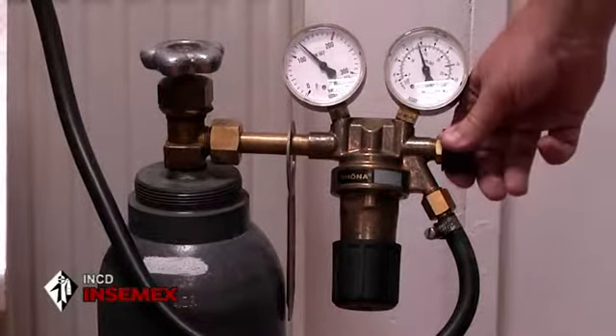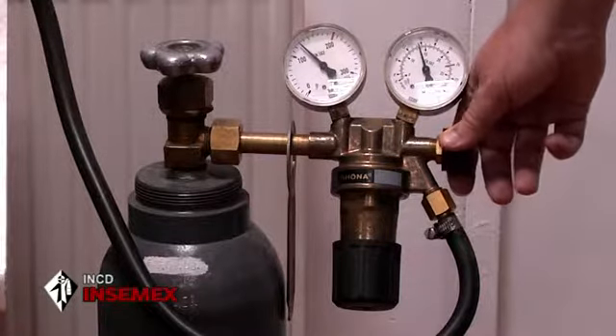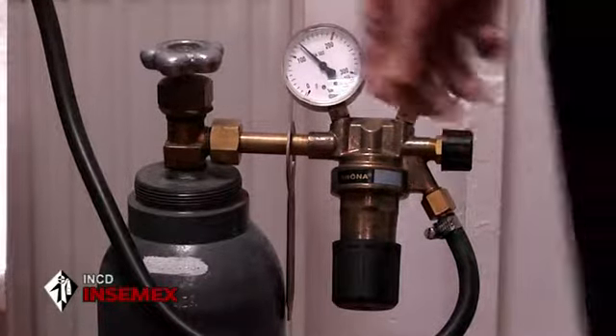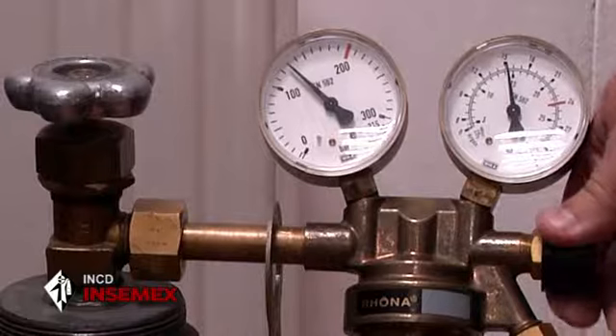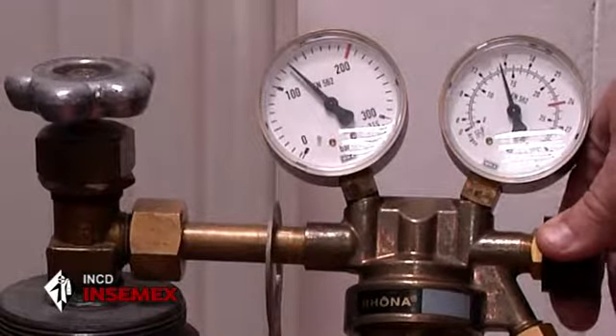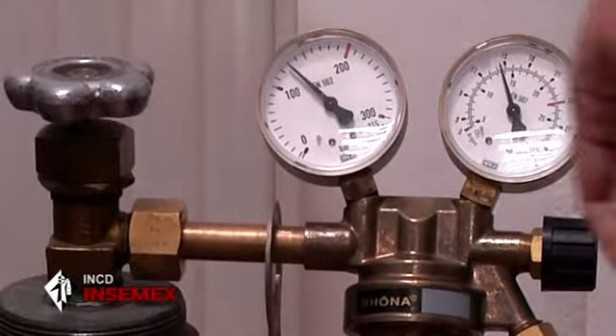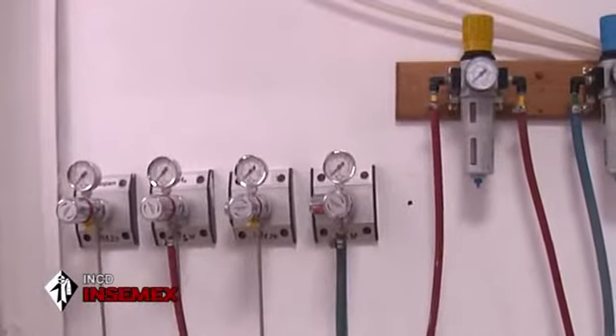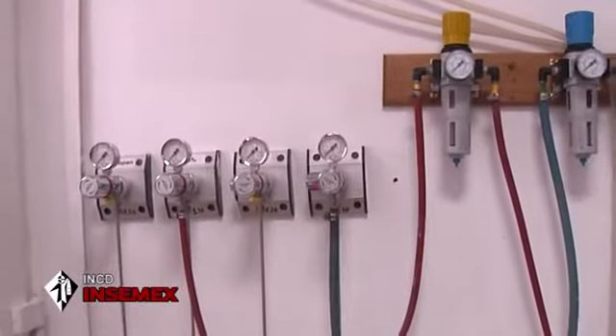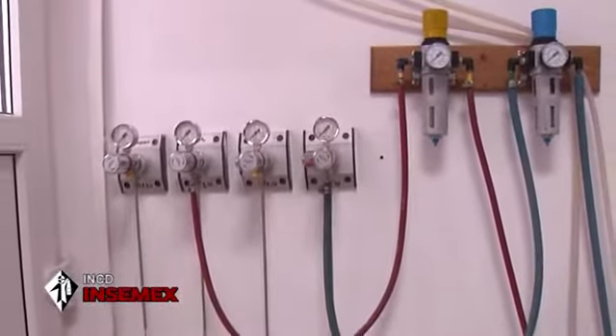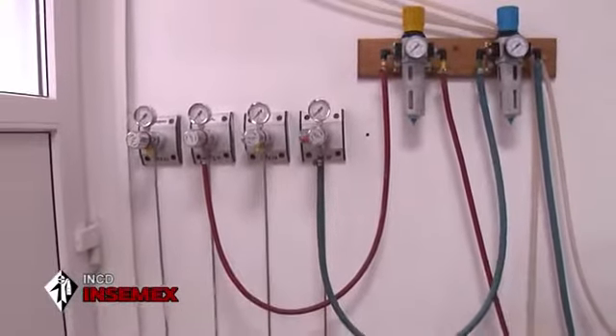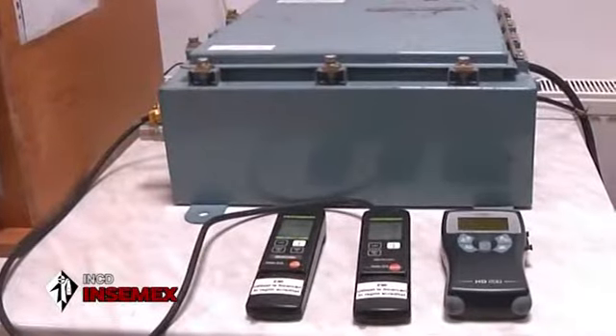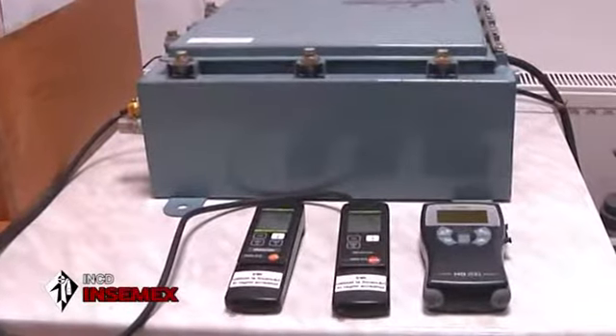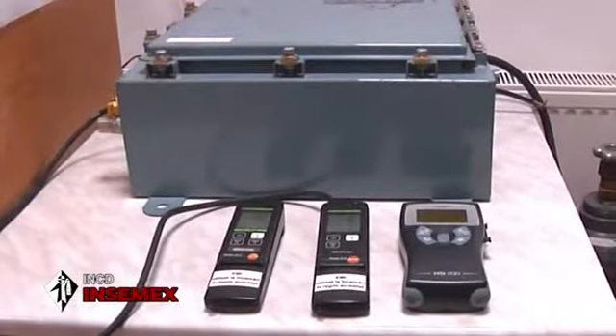Part of the stand is also the equipment for measuring minimum and maximum overpressures and the purging time. The tests are performed in accordance with a specific procedure accredited by the Romanian Association for Accreditation and in accordance with the European Standard 60079 second part. Usually, tests are performed at the manufacturer for large-size equipment, but there can be situations in which the tests are performed in the laboratory.